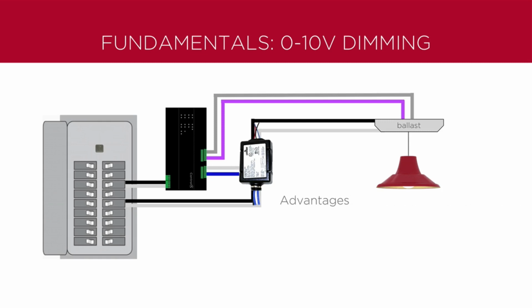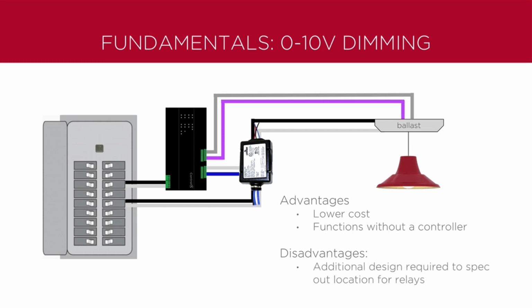The advantages for an external relay are lower cost and that it functions without a Control4 controller. However, additional design is required to spec out a location for these relays, and additional wiring and connections are required. The main disadvantage for an external relay is that they can be forgotten. If external relays are not installed and wired, the fixtures can never be turned off. Once the sheetrock is up, installing an external relay between the 0 to 10 volt module and the fixture itself can be difficult.